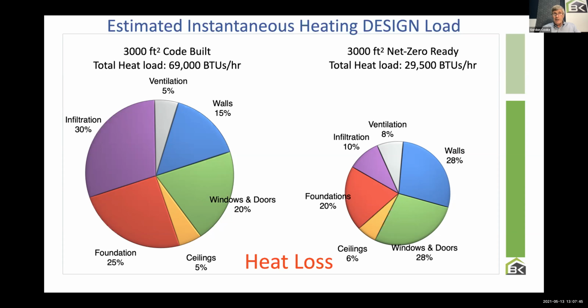So a couple of key words there: estimated. In the same way that we estimate energy, nobody's suggesting that that's actually how much energy you're going to use. When we estimate the heating design load, you're going to say, well, gee, I'd like to be pretty darn close. I certainly don't want to be under. That is, I don't want to be smaller than what I need on the design day. So by definition, when I do an estimated heating design load, I try to be conservative. If there's room to play at all, I try to think about, or at least the programs try to think about, worst case scenarios. So keep that in mind.